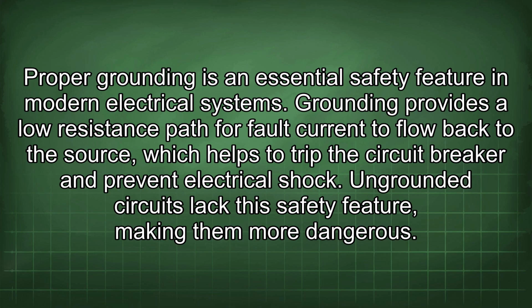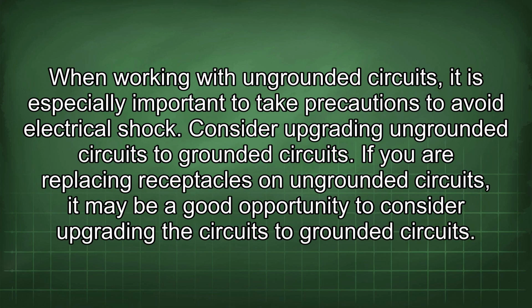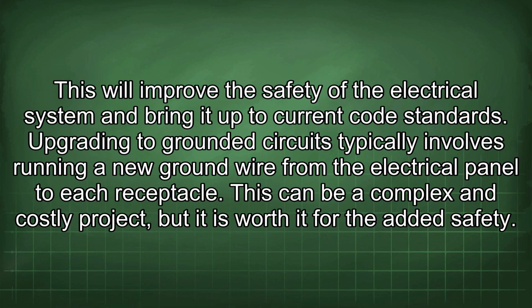Proper grounding is an essential safety feature in modern electrical systems. Grounding provides a low-resistance path for fault current to flow back to the source, which helps to trip the circuit breaker and prevent electrical shock. Ungrounded circuits lack this safety feature, making them more dangerous. When working with ungrounded circuits, it is especially important to take precautions to avoid electrical shock. Consider upgrading ungrounded circuits to grounded circuits. If you are replacing receptacles on ungrounded circuits, it may be a good opportunity to consider upgrading the circuits to grounded circuits. This will improve the safety of the electrical system and bring it up to current code standards.